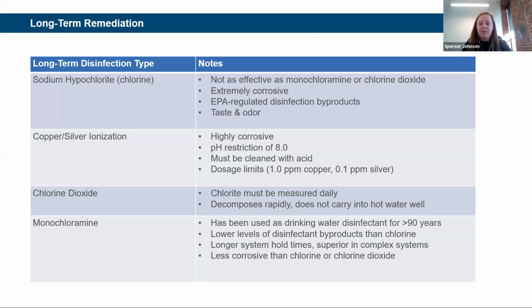It has lower levels of disinfectant byproducts than chlorine, and we like to think of monochloramine as a lazy disinfectant. It stays in the hot water and that residual stays in the water longer, so we see it throughout both your cold and hot water systems. It gives you that good residual throughout, and it's less corrosive to your plumbing system than chlorine or chlorine dioxide. So we've seen it be really successful with Legionella bacteria.